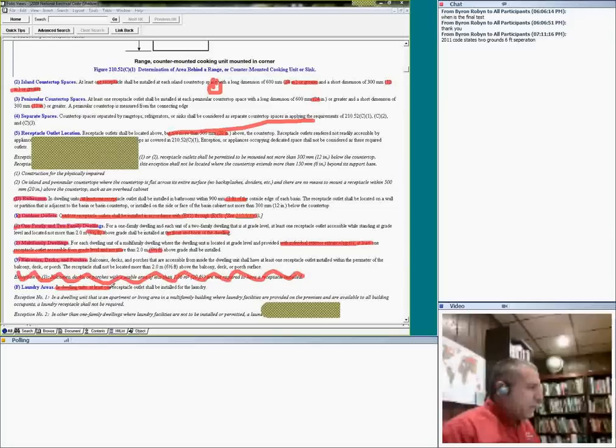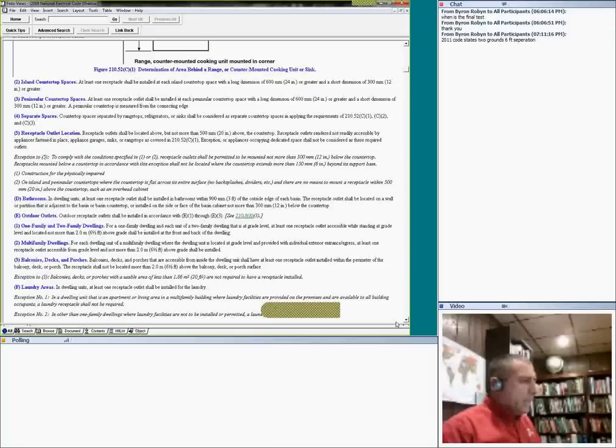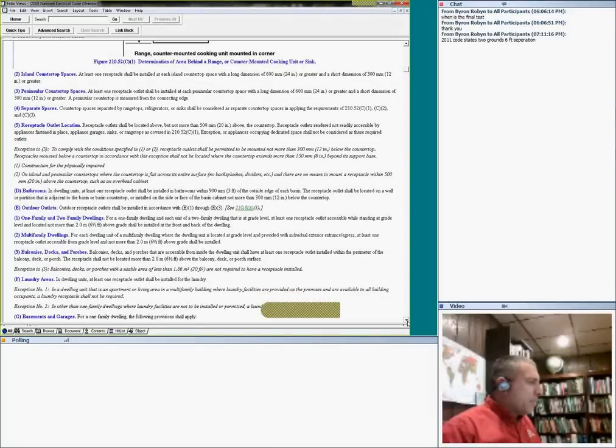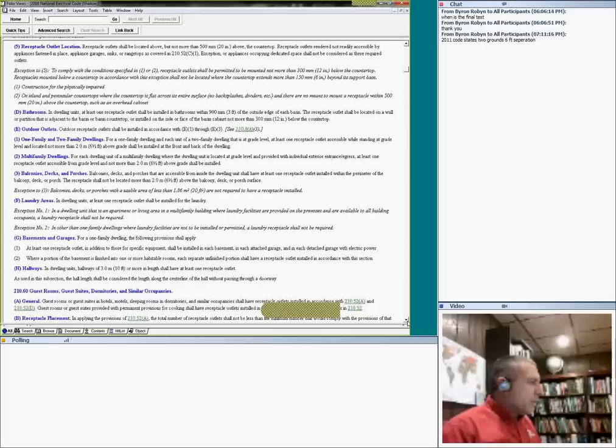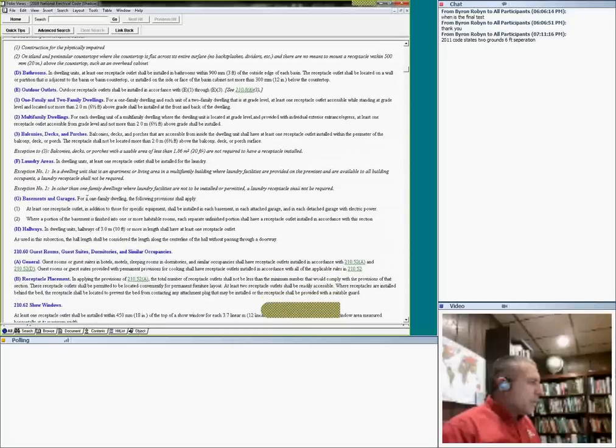In units, you need 1 receptacle for the laundry room, and we all know why. These are a few things, guys, to remember. Laundry room. You need a receptacle. In a 1 family dwelling, at least 1 receptacle in the basement in addition to any others. Where the basement is divided, you might need different receptacles. Hallways: a receptacle every 10 feet; if the hallway is 10 feet or more, you need one receptacle.